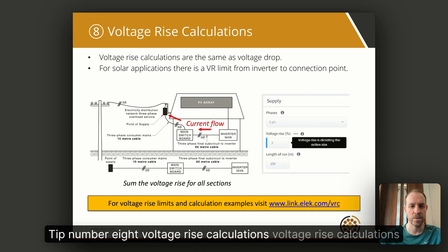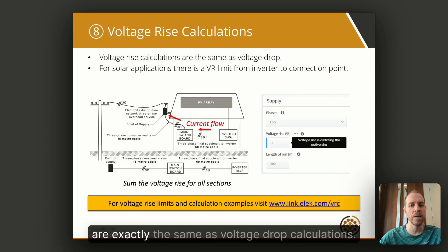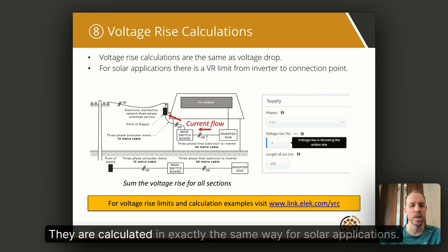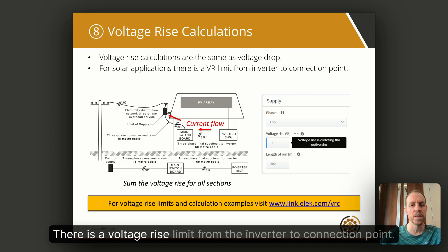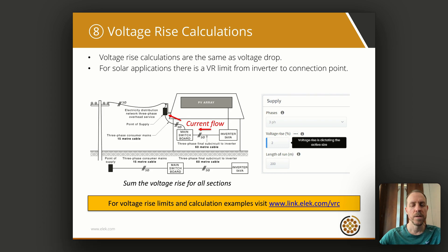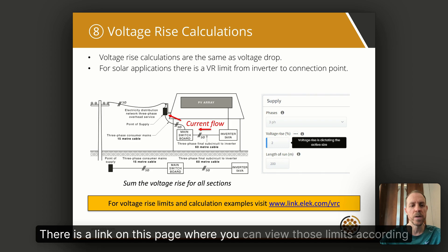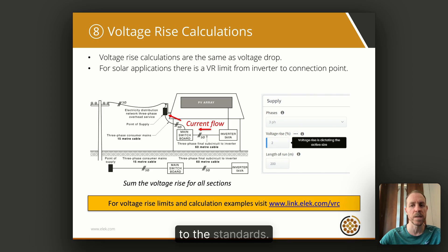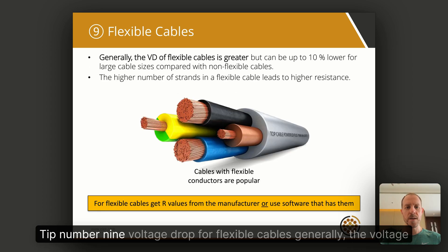Tip number eight: voltage rise calculations. Voltage rise calculations are exactly the same as voltage drop calculations — they are calculated in exactly the same way. For solar applications, there is a voltage rise limit from the inverter to the connection point. There is a link on this page where you can view those limits according to the standards.